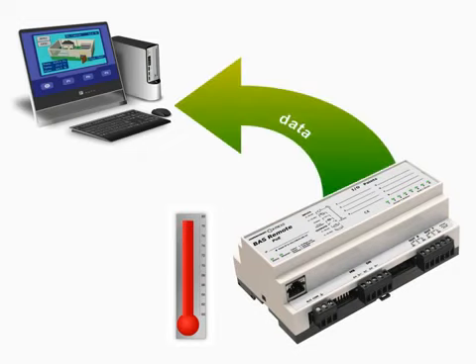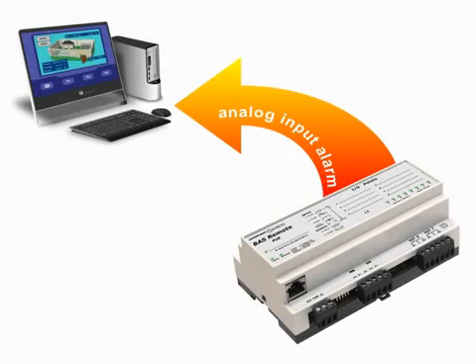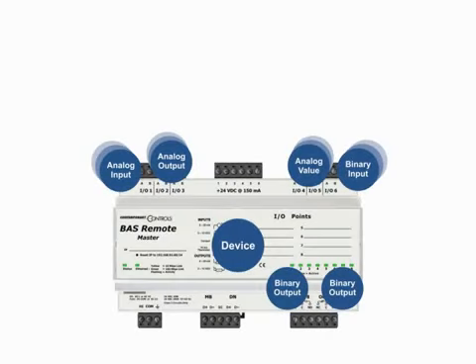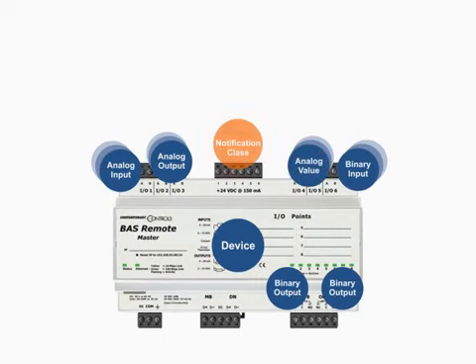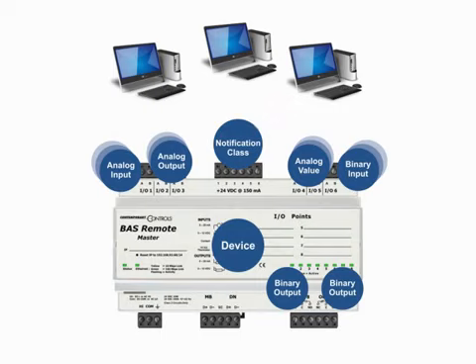The next area is alarm and event management, which defines the exchange of data based on predefined alarm limits or event triggers. An alarm or event notification process is as follows. An object detects that an alarm has occurred. Using a notification class object, the object determines when and where the alarm is reported. An event notification message is sent to one or more alarm recipients. Notifications await acknowledgement by the recipient if they are confirmed notifications.